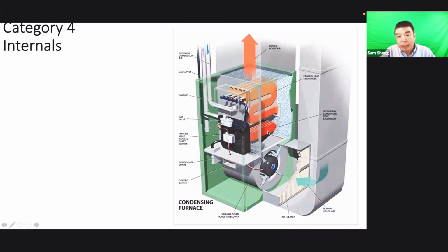Yeah, so there's aluminum fin there. It's a small space. When the air blows through here, even if we have the filter, some dust still goes through the blower motor and collects at the bottom of the coil. If it's dirty here, it has the same symptoms as a clogged filter. The high temperature sensor will sense the heat and trip the high limit switch.